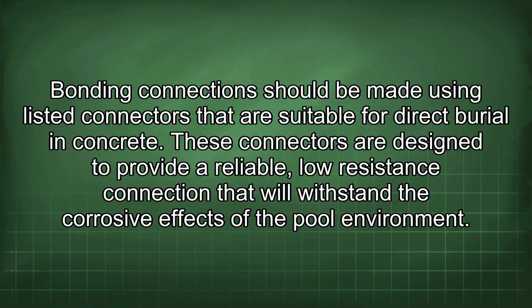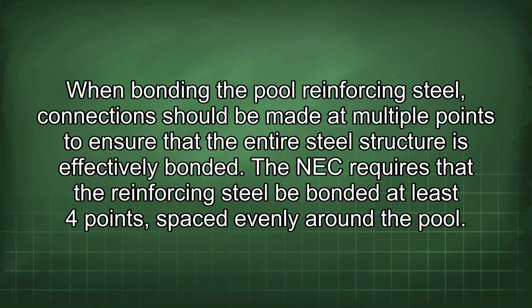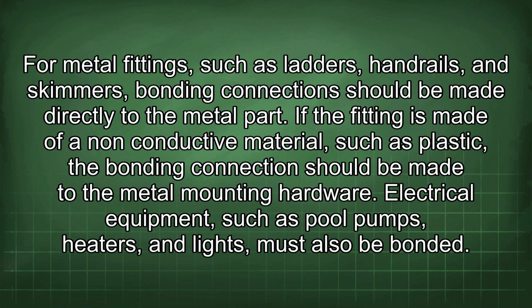Bonding connections should be made using listed connectors that are suitable for direct burial in concrete. These connectors are designed to provide a reliable, low-resistance connection that will withstand the corrosive effects of the pool environment. When bonding, the pool reinforcing steel connections should be made at multiple points to ensure that the entire steel structure is effectively bonded. The NEC requires that the reinforcing steel be bonded at least 4 points, spaced evenly around the pool. For metal fittings such as ladders, handrails, and skimmers, bonding connections should be made directly to the metal part.